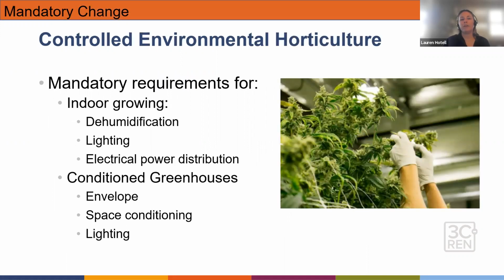Jumping into controlled environmental horticulture. So this is a mandatory change. This was a new section that was added to address indoor growing in conditioned greenhouses, mainly with a focus on cannabis growing. So a lot of these changes cover electric lighting for growing plants. They now have to have a high photosynthetic photon efficacy, or PPE, which is spectrum efficient for growing plants. So you're able to grow plants at a higher efficiency lighting system, saving energy for everyone. And they also have to have dimming and time clock controls.